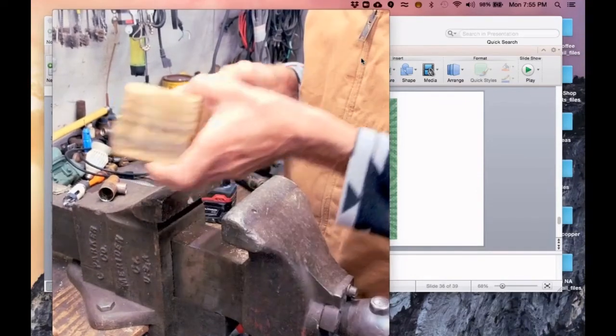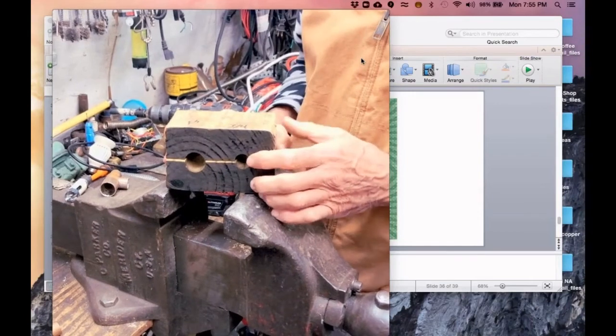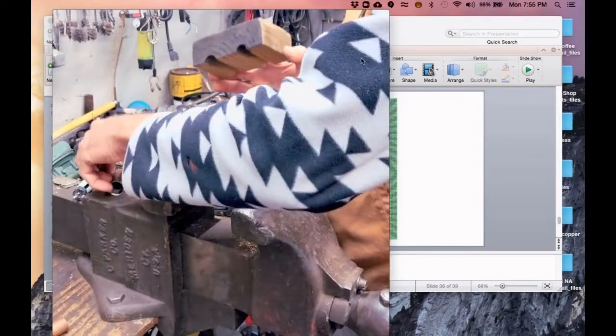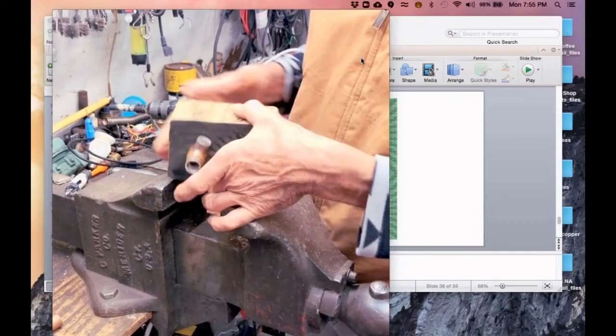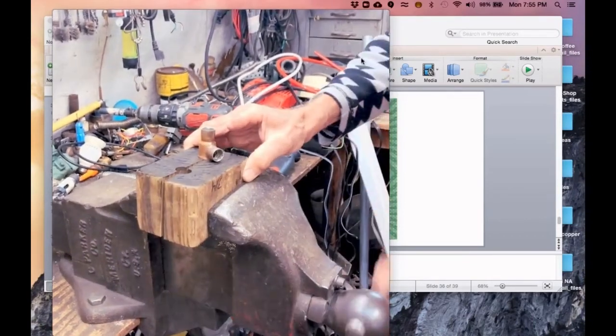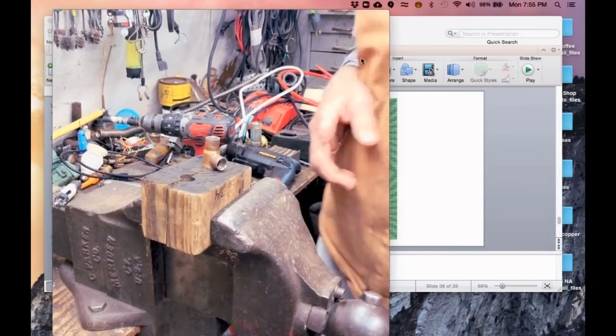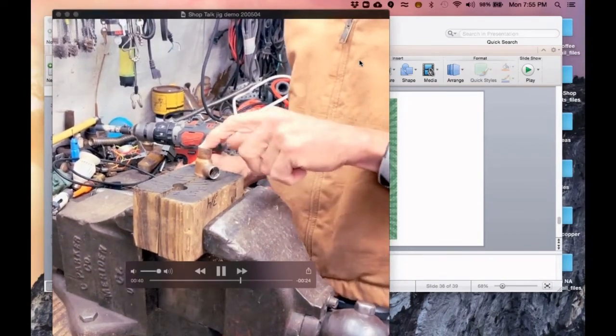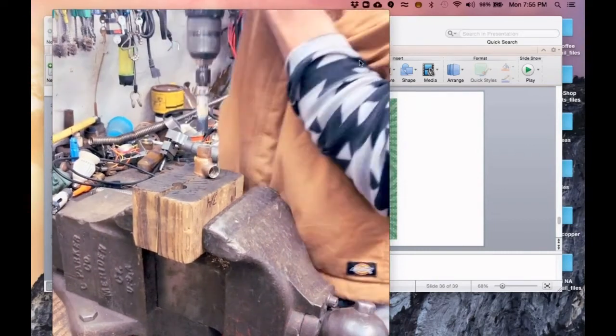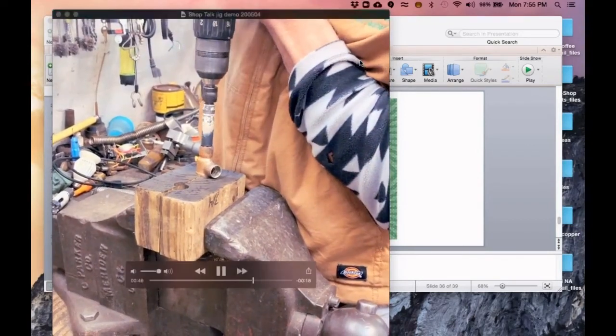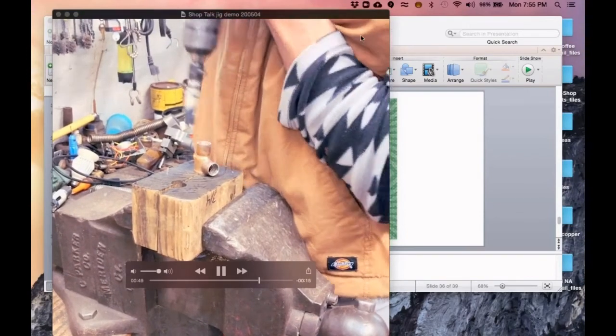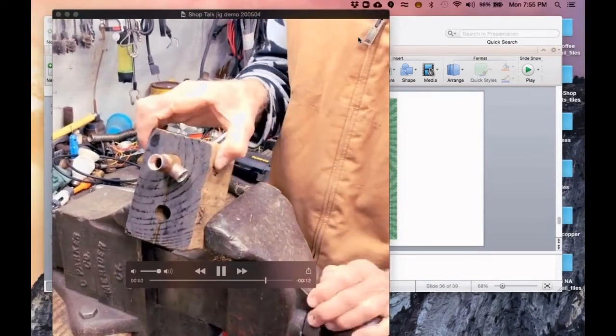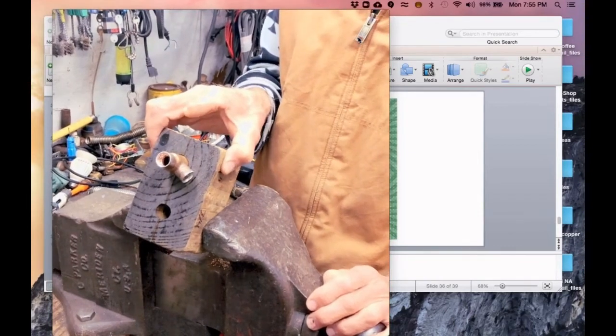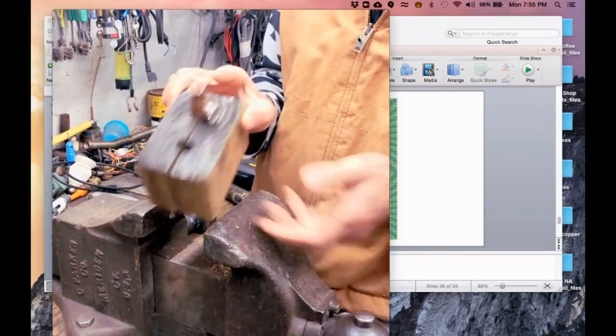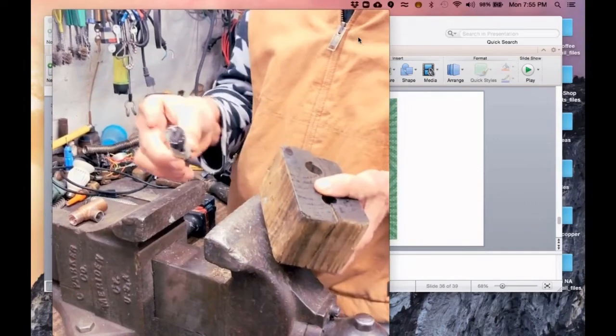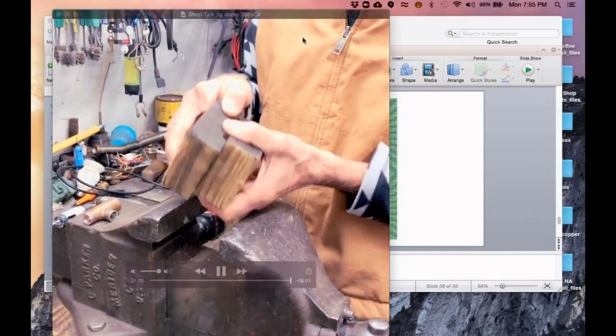And then what I did on the other end here is this is a 3/4 hole here, and this is a 1-inch hole. And so what that allows me to do is put a fitting in here like this, and I can put this in the vise. Since I'm frugal or cheap, I use the fittings over and over again. Some of these fittings I've used probably a dozen times, and now if I want to get the solder out of there so I can use it again, I just take a 5/8 hole saw like this, clean it out, and there's a perfectly reusable fitting. Some of these I've had probably for years that I've just taken apart and used over and over again. So block of wood, couple hole saws, there you go.